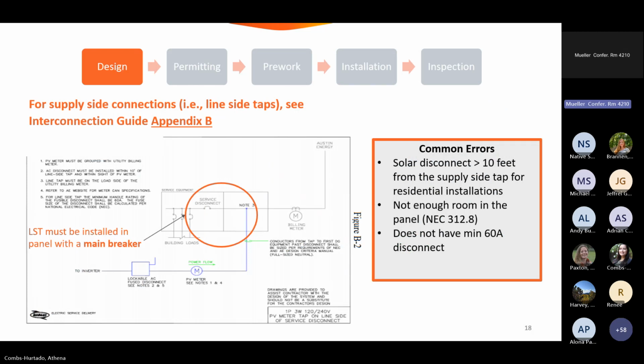Okay, for supply side connections, this is in the interconnection guide, Appendix B. You've got to have a main breaker in the panel if you're doing a supply side connection. You need a fuse disconnect, obviously, and it might be surprising to you that the PV meter is the first component after the tap, which will be on the load side terminals of that PV meter. Some common errors are that the disconnect is greater than 10 feet from the supply side tap. So it's got to be within 10 feet, or there's not enough room in the panel. I think our next slide will speak to that. Or your disconnect on a supply side tap is not at least 60 amps. That's not the fuses inside, that's the actual enclosure itself. It's got to be 60 amps. All right, next slide.